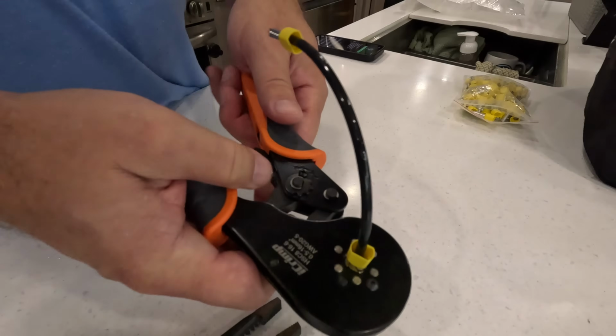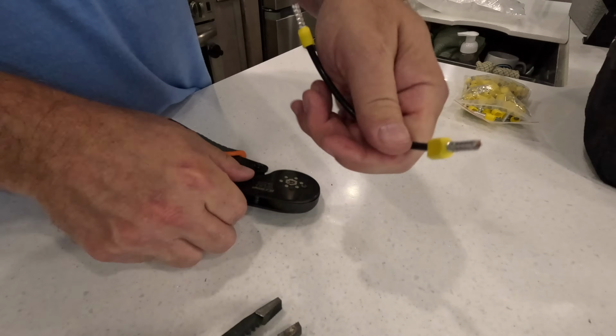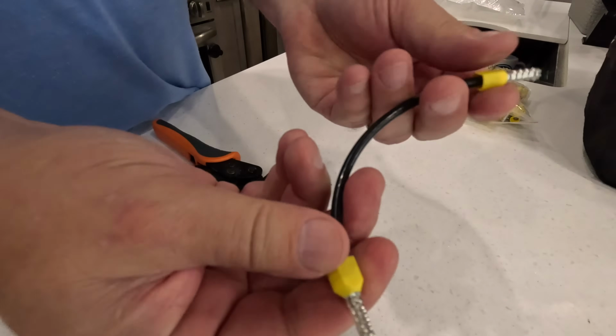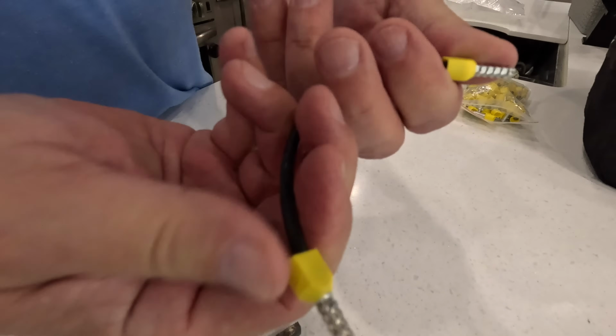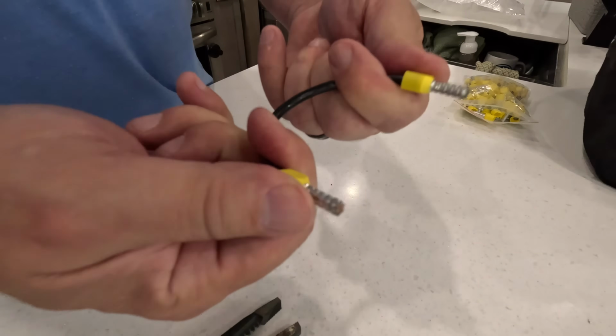As I mentioned, I did it at the ATS, the automatic transfer switch, and I just used a 10 gauge wire with 10 gauge ferrules on the end. I use 10 gauge because this thing is only ever going to have a maximum of 3,000 watts or 25 amps going through it. So 10 gauge is fine for that. Coming out of the ATS, of course, that's 6 gauge. So that fixes our issue of generator power accessibility. But I now have that full power of the generator available on line 1.